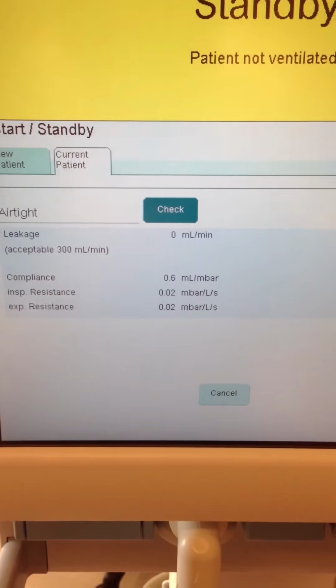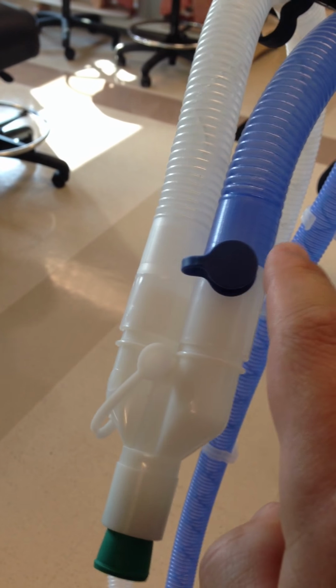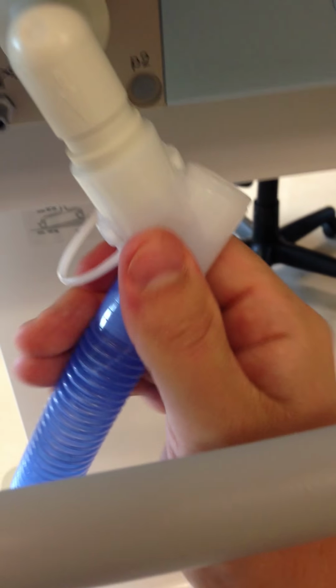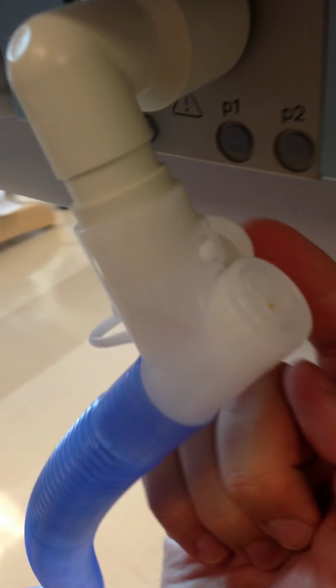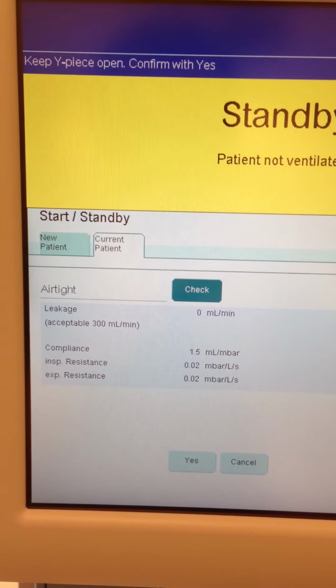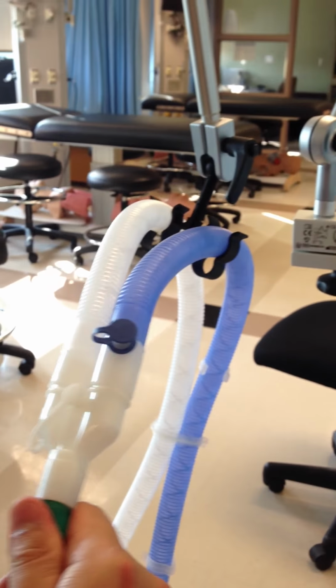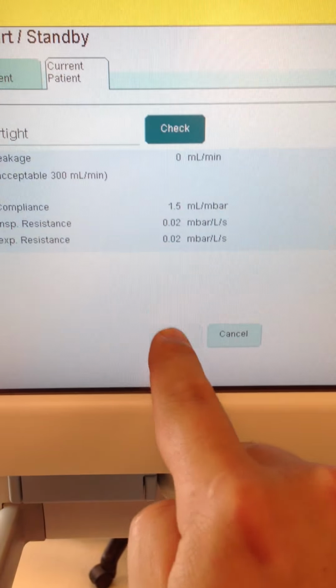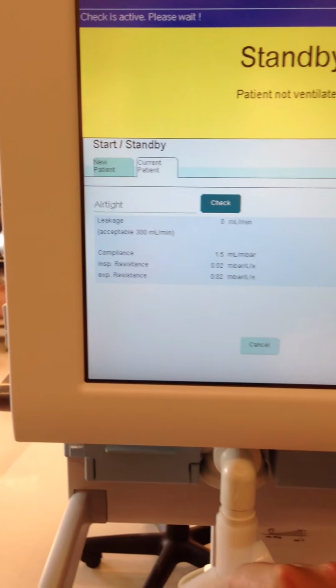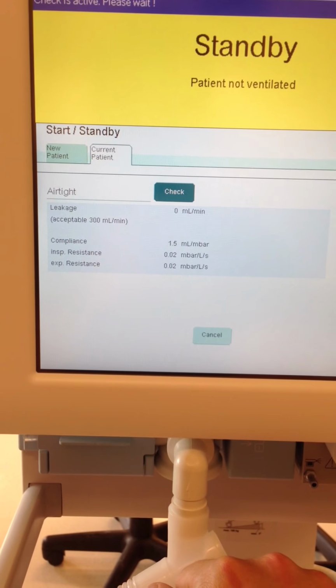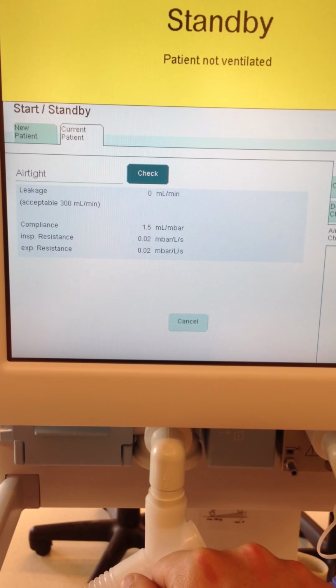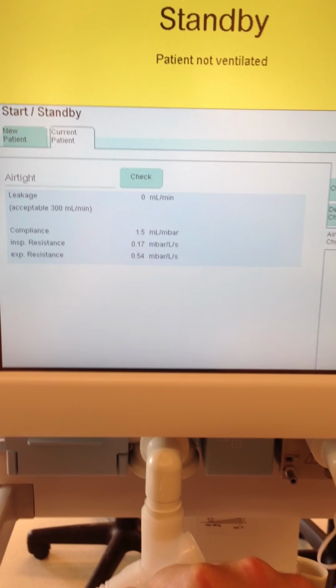That's the acceptable range. So if there is a leak, often you can troubleshoot it. Look for these caps to be open or half closed. Make sure your fittings are all tight on your inspiratory and expiratory. There's another cap on the back here on this circuit. That would be for your chamber if you were using one. And now it's asking us keep Y piece open and confirm with yes. So I'm just going to pop out my cap, hit yes. And now it's going through a compliance, inspiratory and expiratory resistance check. And that's it.